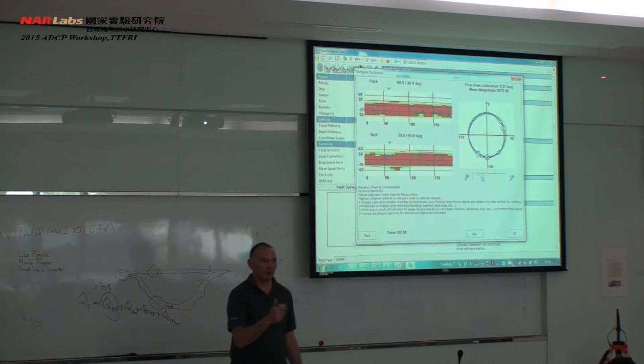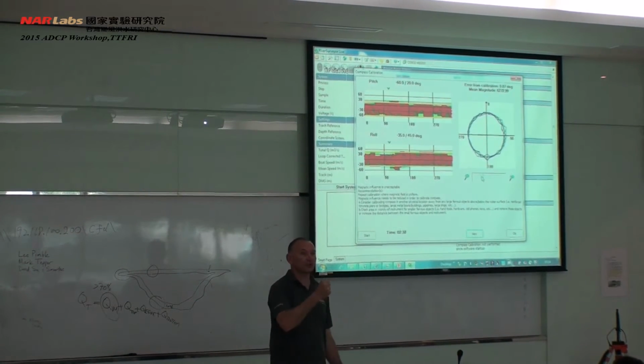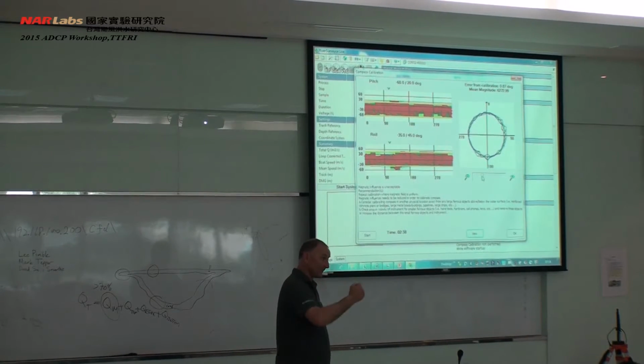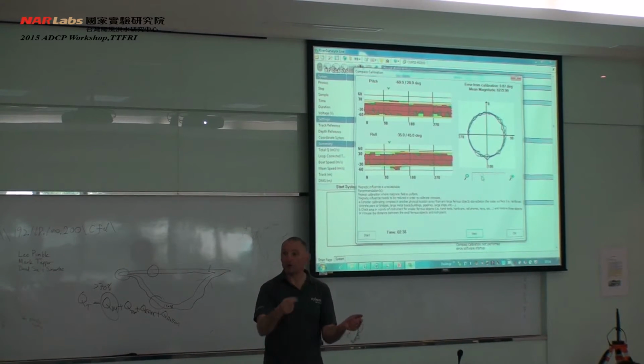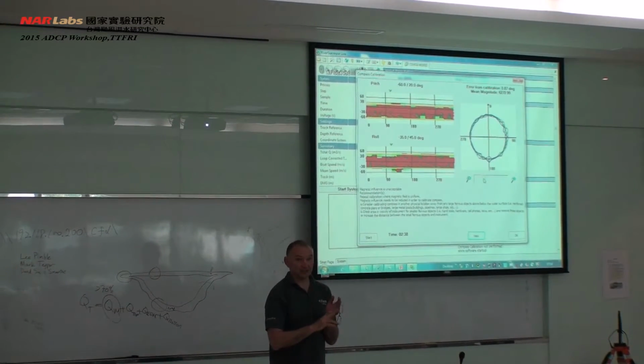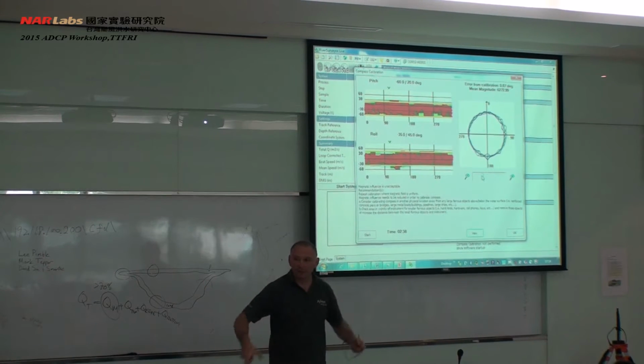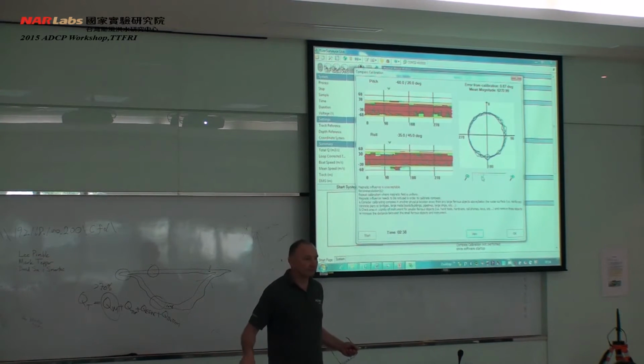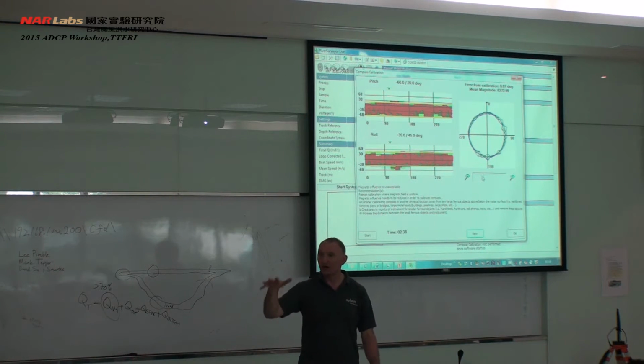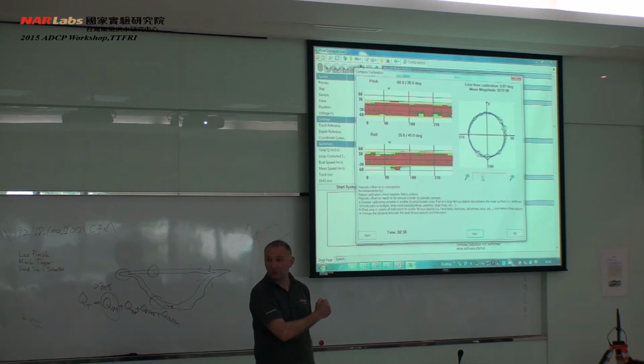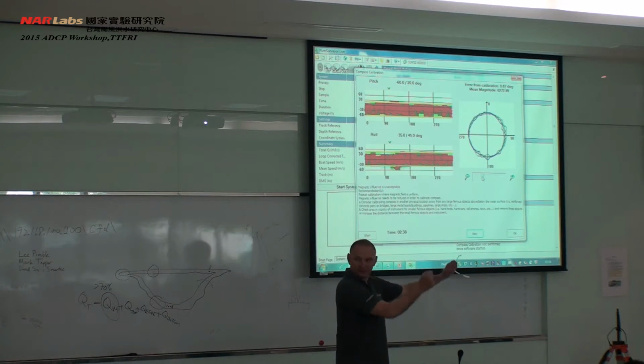The most common error that people make is they want to do a measurement from a bridge, so they do their compass calibration on the bridge. Most bridges have a lot of metal in them. A concrete bridge has metal reinforcements inside it. A lot of bridges are iron bridges. There are very few wooden bridges that haven't even got steel bolts, nuts, screws in them. So I would never recommend anybody to do a compass calibration on the bridge, even if you're going to be doing your measurement from the bridge. Go down to the side of the river, away from the bridge, do your calibration down there, and then put the instrument onto the water.